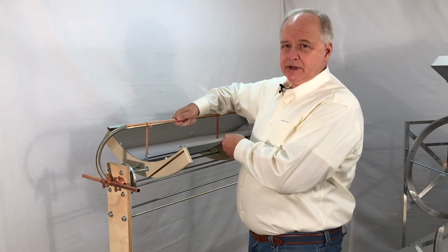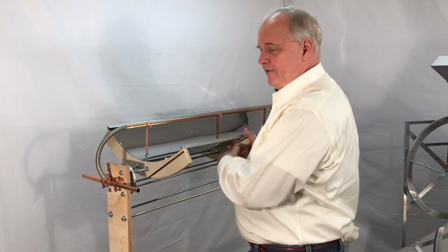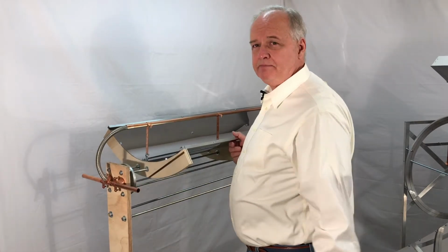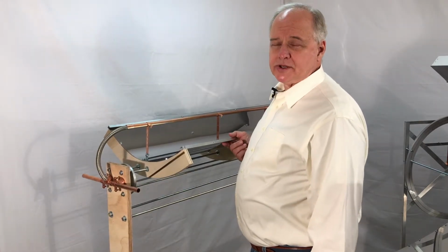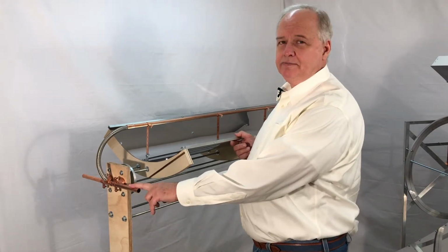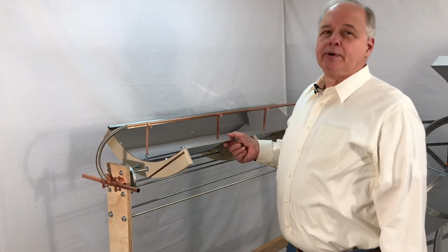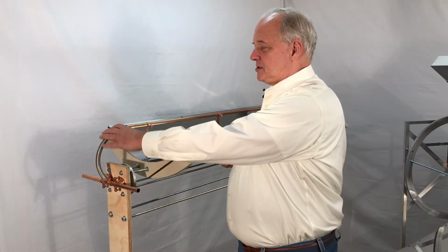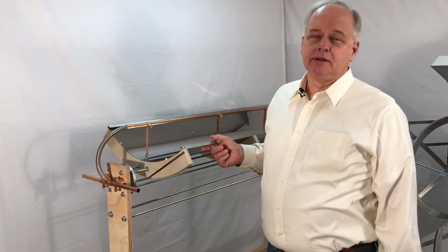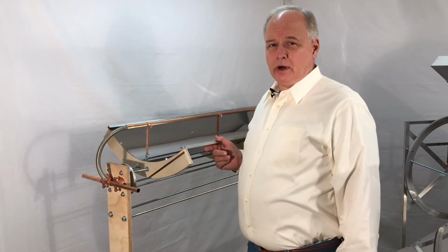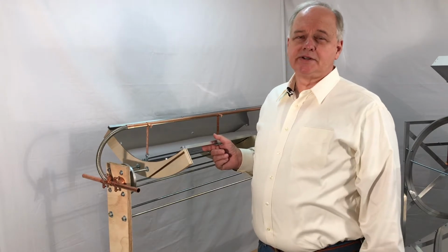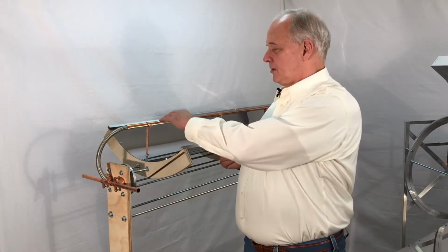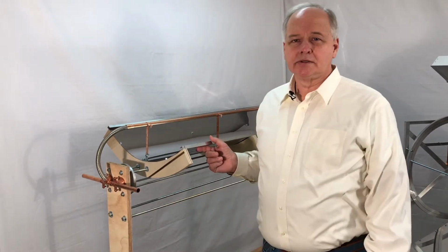The 750 degree synthetic oil is then piped via manifolds to a heat exchanger, which uses the hot oil to generate superheated steam. This transfer of energy causes a 15% loss of efficiency. Superheated steam for generating electricity has temperatures and pressures which are not compatible with flexible connections. In addition, the properties of the synthetic oil limit the upper temperature range to 750 degrees Fahrenheit. Beyond that temperature, oil decomposition accelerates, adding life cycle costs.